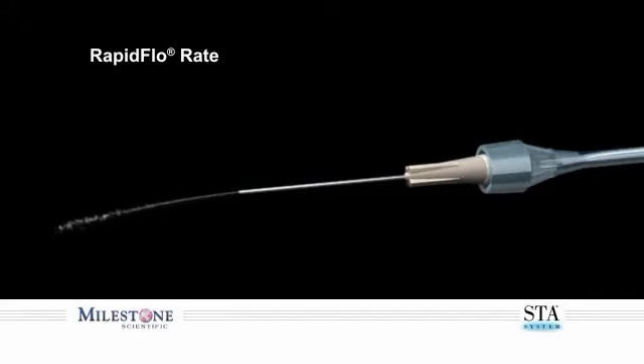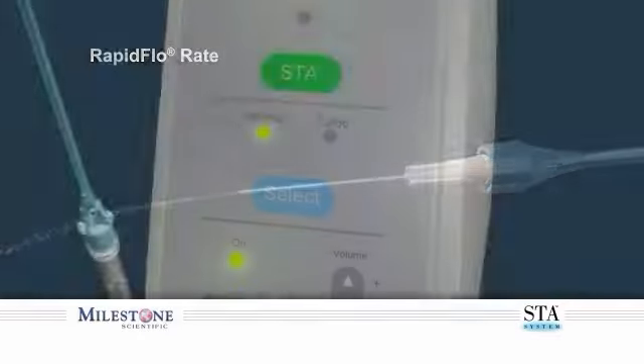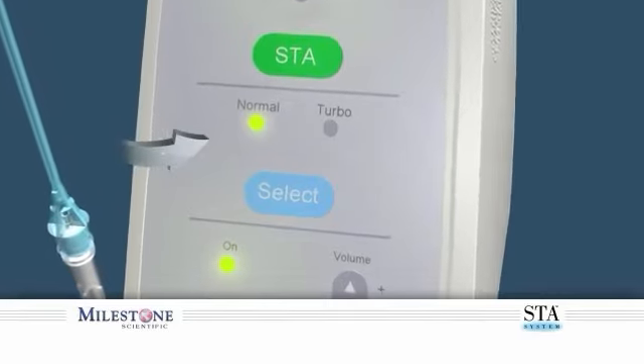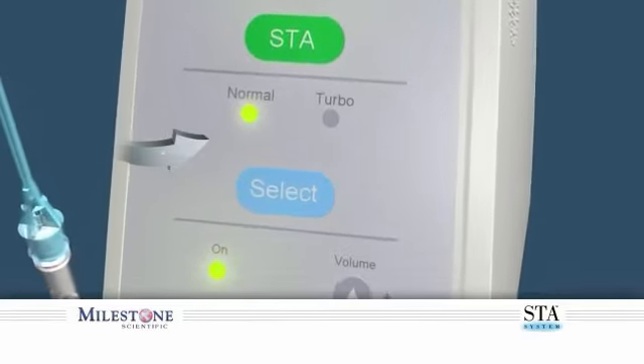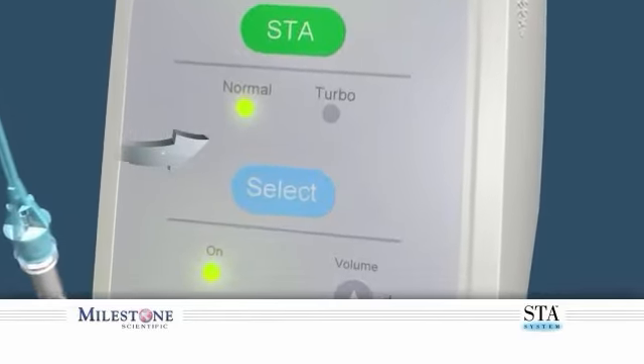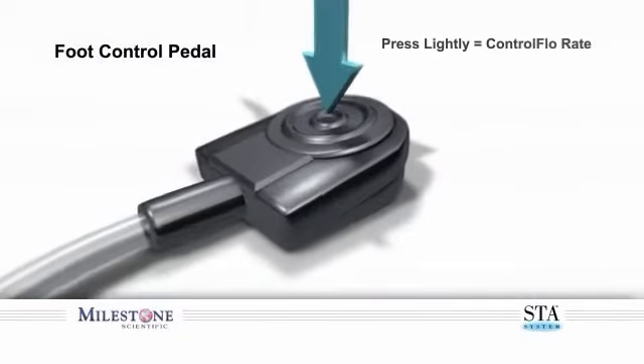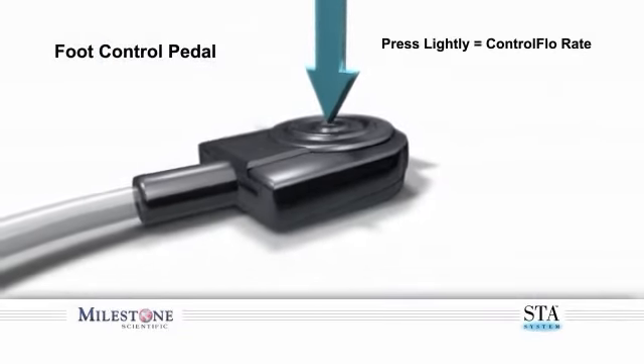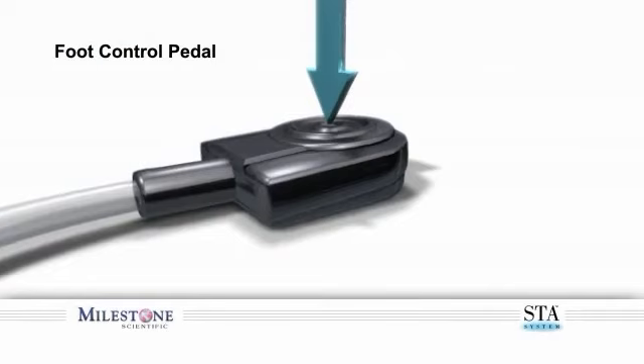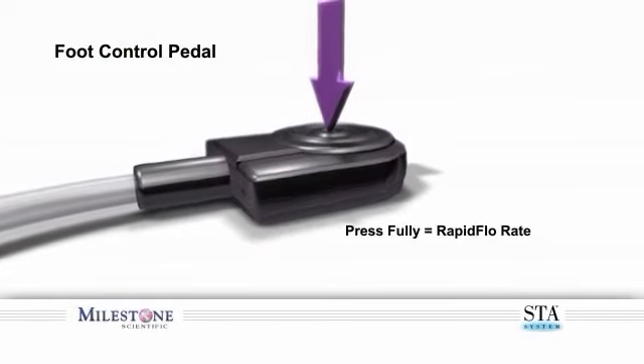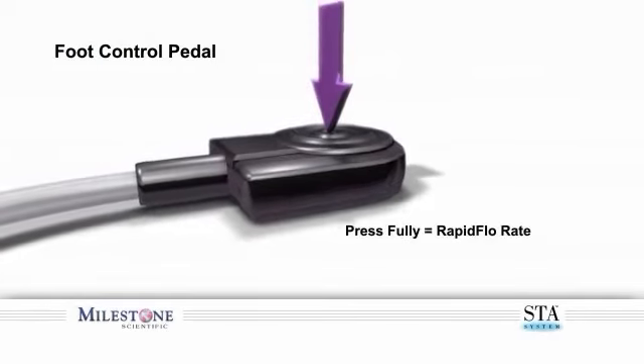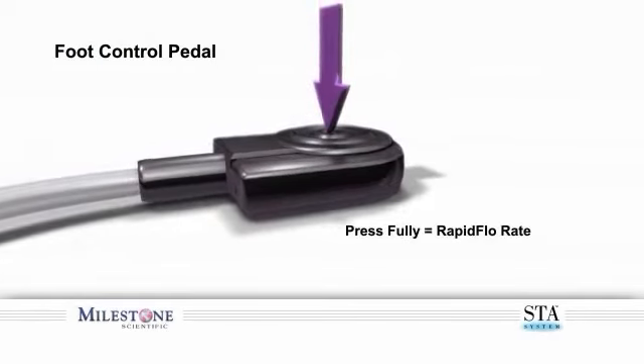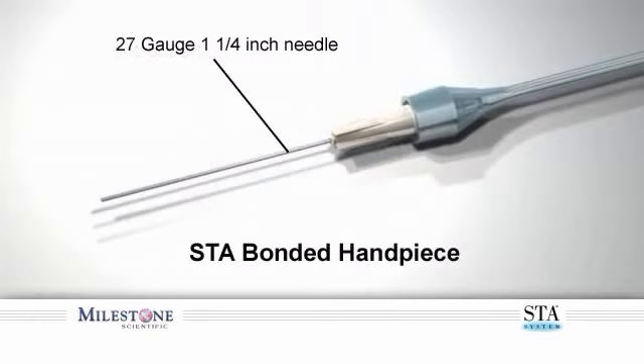In the normal mode, the foot control has two distinct positions. Depressing the foot control lightly allows you to enter the controlled flow rate. Fully depressing the foot control allows you to enter the rapid flow rate. It is recommended that you use a 27-gauge, 1-1/4-inch needle to perform the inferior alveolar nerve block.